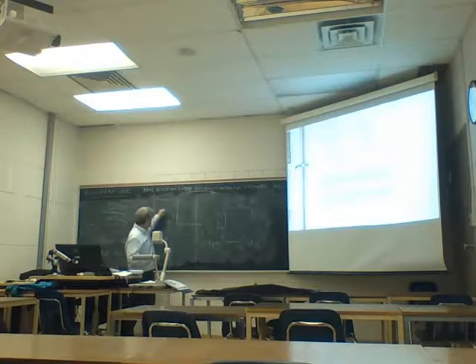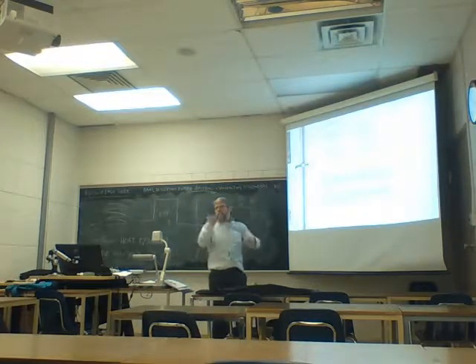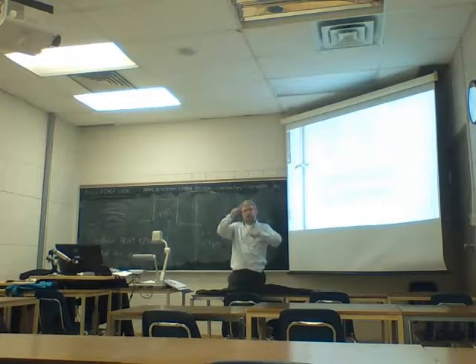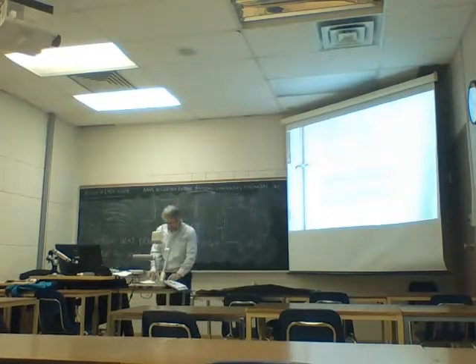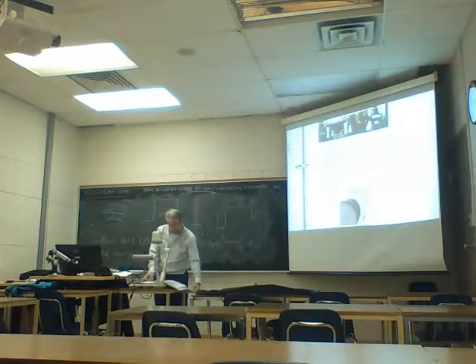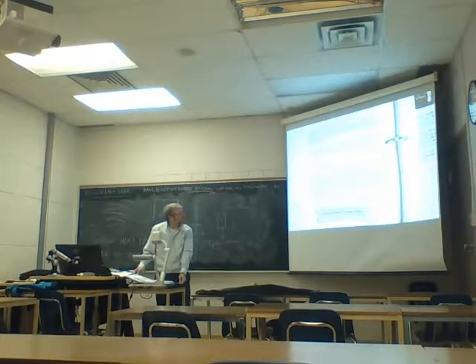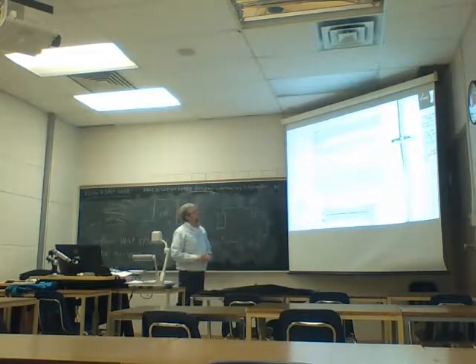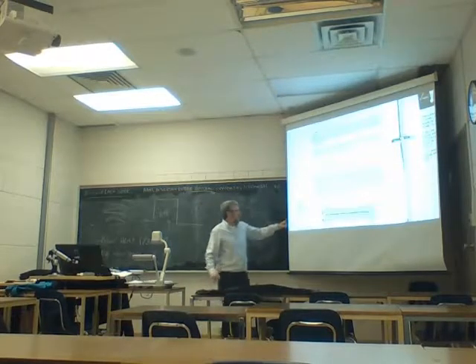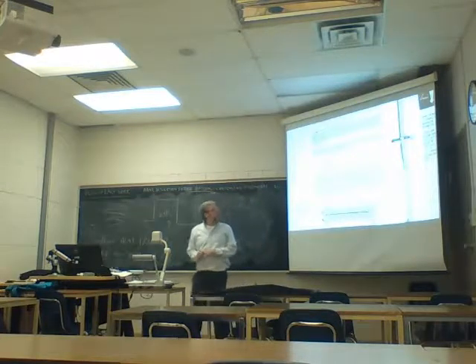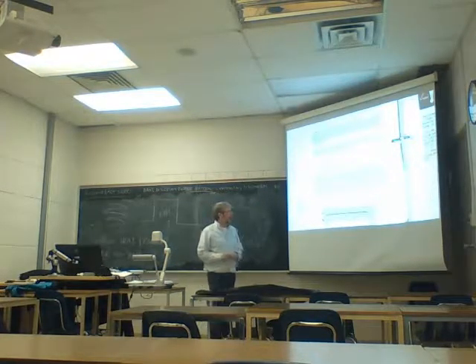How do we allow for expansion in our shell and tube heat exchanger? We got a fixed tube sheet and a U-tube sheet. This is the U-tube. Basically, this U-tube is held rigidly here, and it's allowed to expand that way. So it expands like this. This is what we call a two-pass. Really, one tube, single pass heat exchanger.